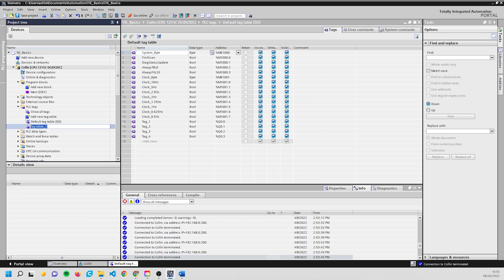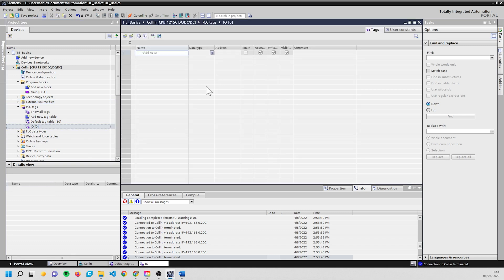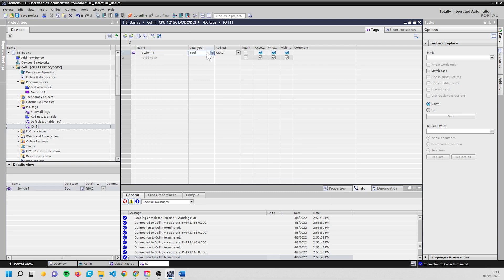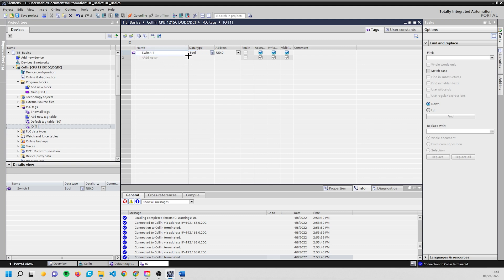And we're going to call this I/O just to simplify things. So in I/O what we're going to do is just do the switches - so I know we've got more but we're just going to do the eight switches we have. I'm going to show you a cute little trick here. We're going to call this Switch_1. Data type is a bool and automatically it's put the input address starting at 0.0 - so that's the first switch. We could just write all of these in down, but because it doesn't work all the time, it depends where it is. But generally if the number's at the end, you can just get this and drag it down, and it should auto increment that number.